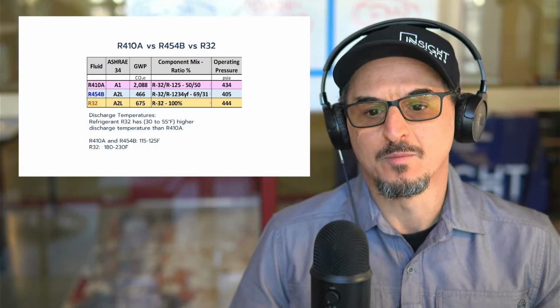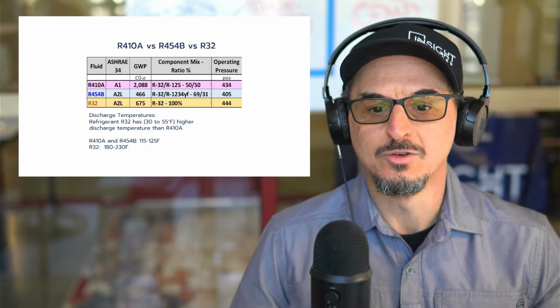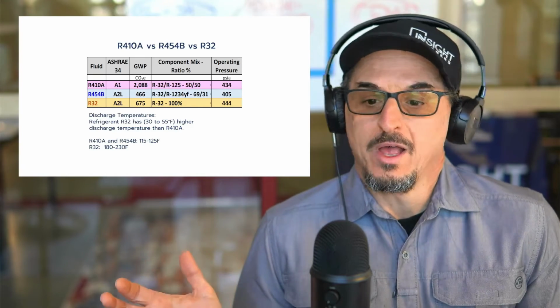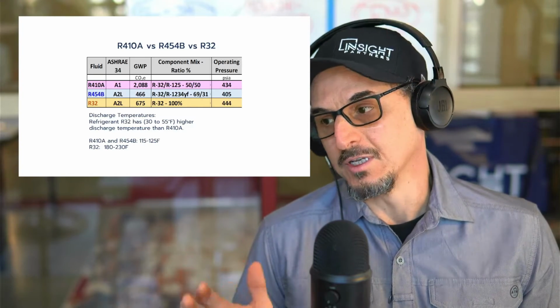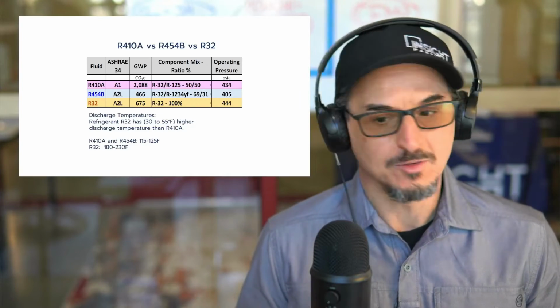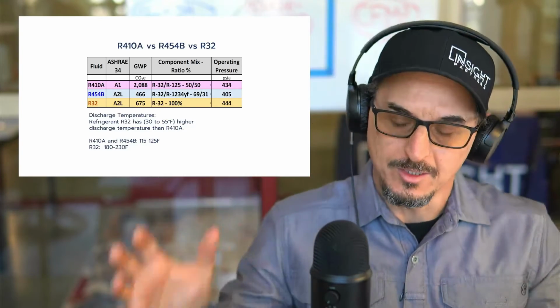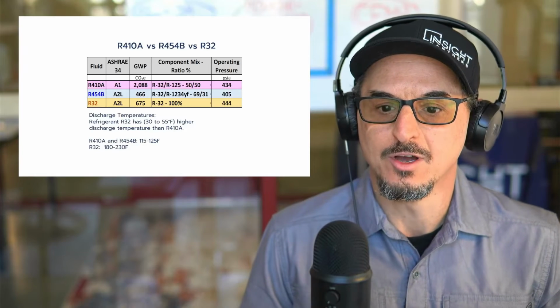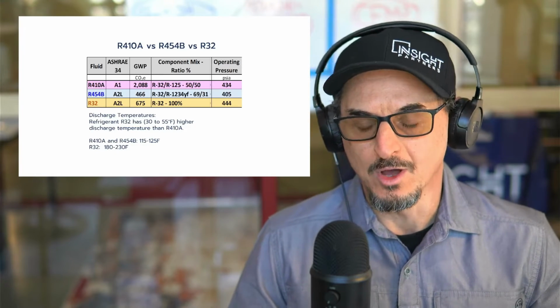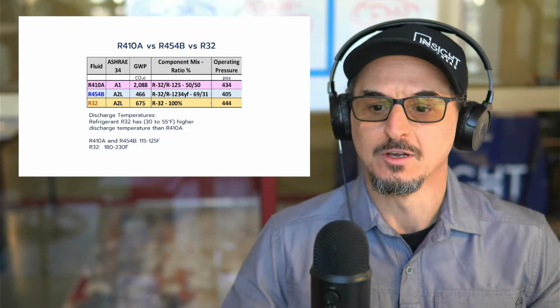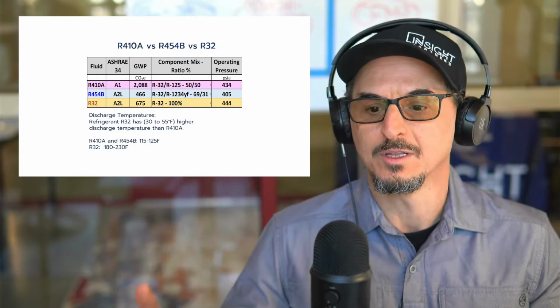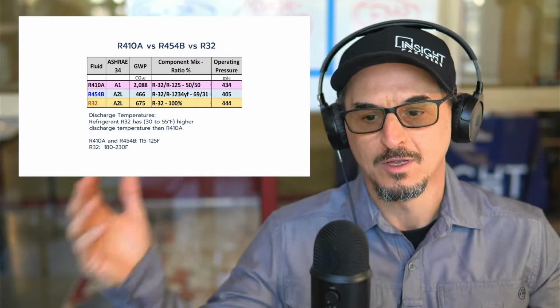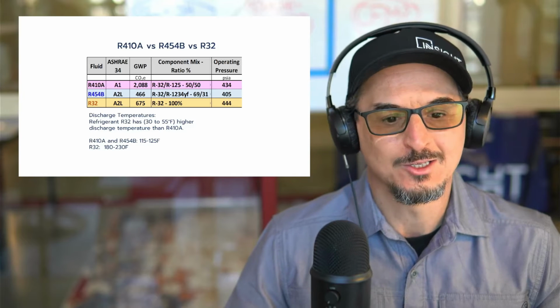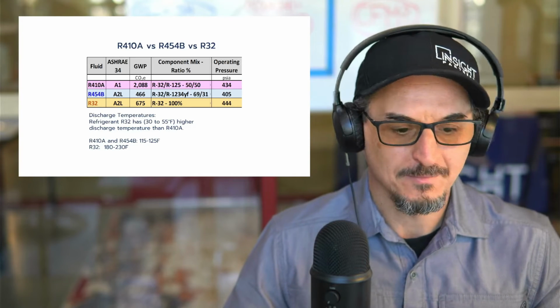The 454B is similar to other blends we use today - it's a non-azeotropic blend, which means no matter where it is in the system, it's typically at the same ratio of 69 to 31. That's important because if you're servicing equipment, if it leaks, it's going to leak typically in the same ratio, so you don't have to take all the refrigerant out of the machine and put a whole new batch in. That's super important when you're looking at that.